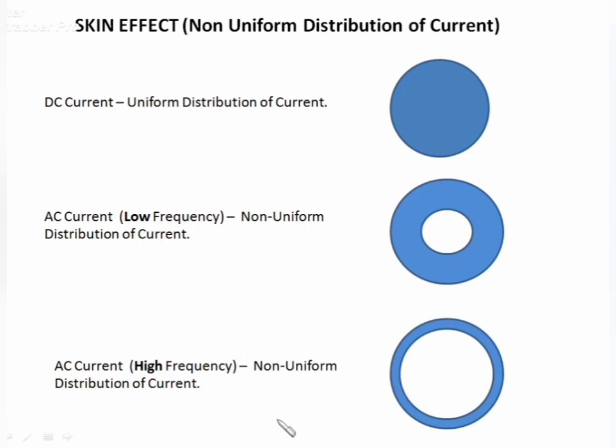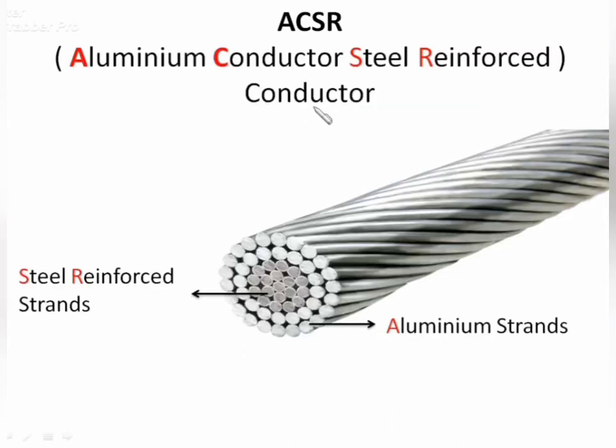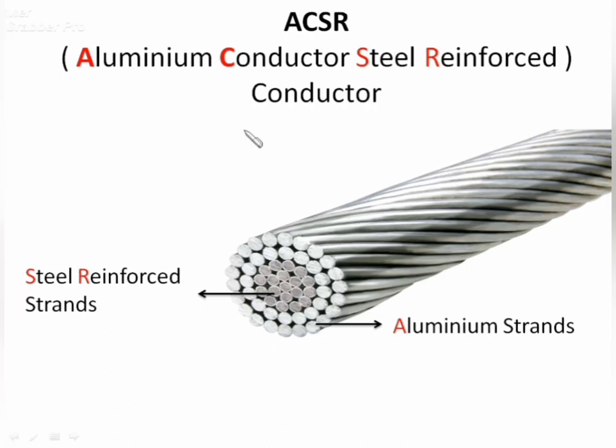It can be concluded that as frequency increases, the conductor is less utilized with respect to current flow. In ACSR conductor, the central steel strands are reinforced specially to provide strength to the conductor, and the major current flows through the aluminium strands. Hence, it can be said that skin effect has lesser contribution in ACSR conductor.